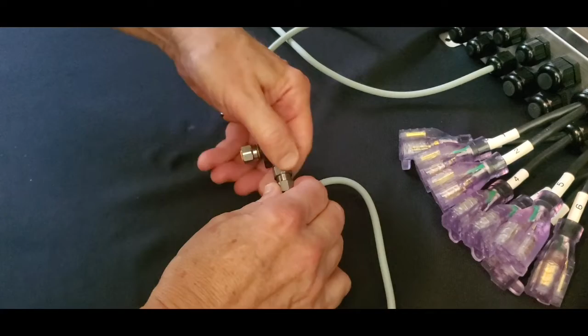Now, if you'd like to add a third or fourth probe, simply add on another T exactly like you just did. You can have as many T's as you have channels on your controller. After you've done the T's, you can add your probes, one, two, or three, but not at the same time. You'll want to put your first probe on, go to your controller and program it, then your second on, program it, and so on.